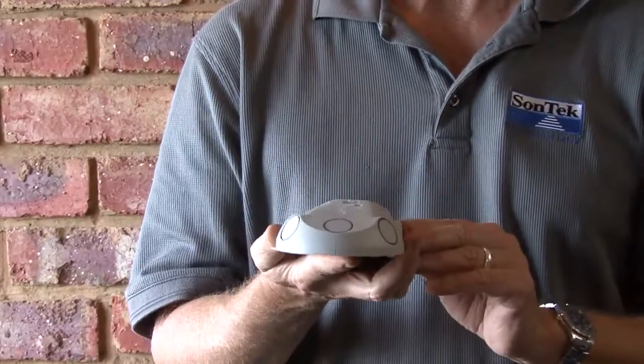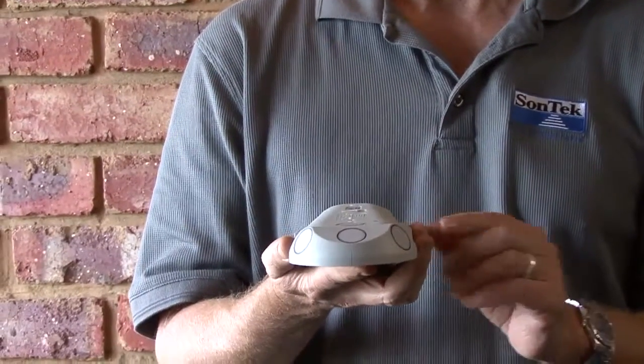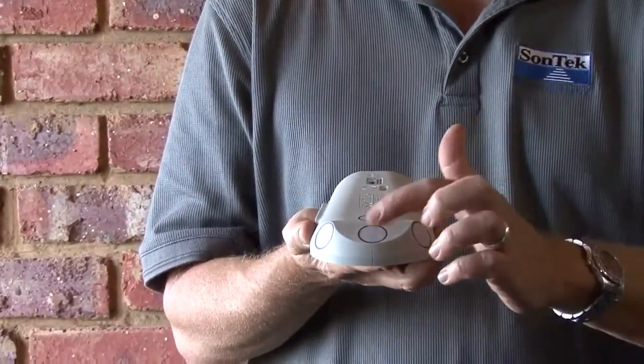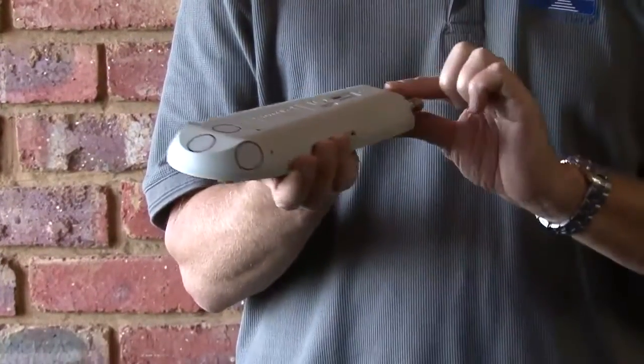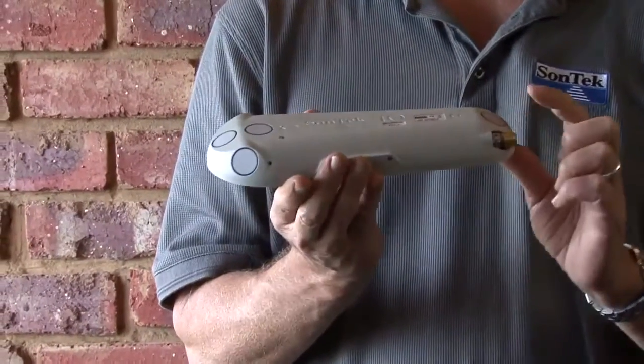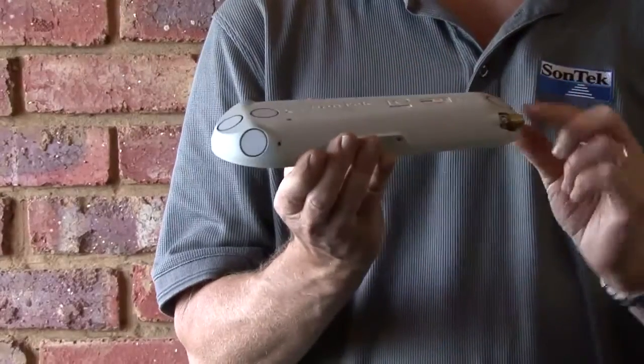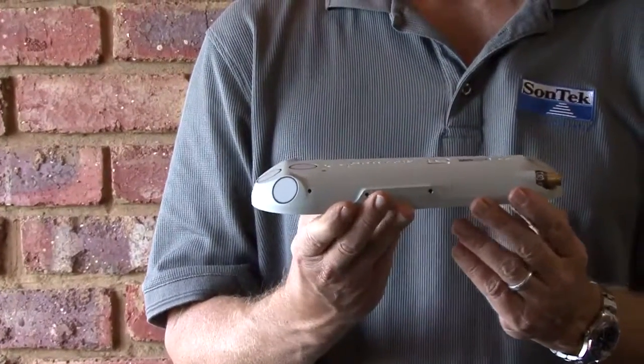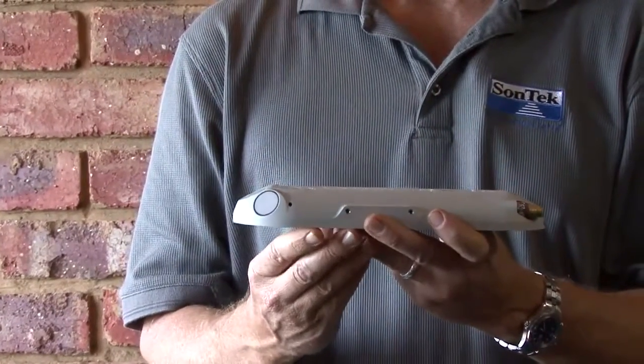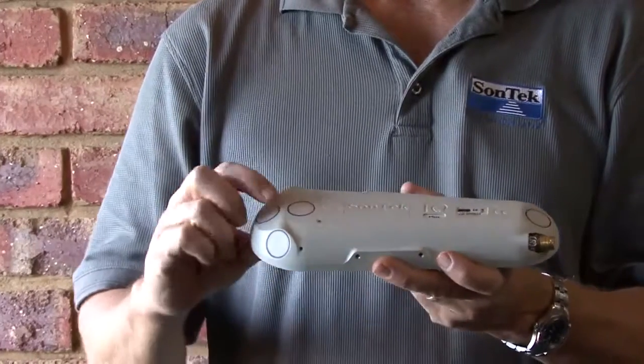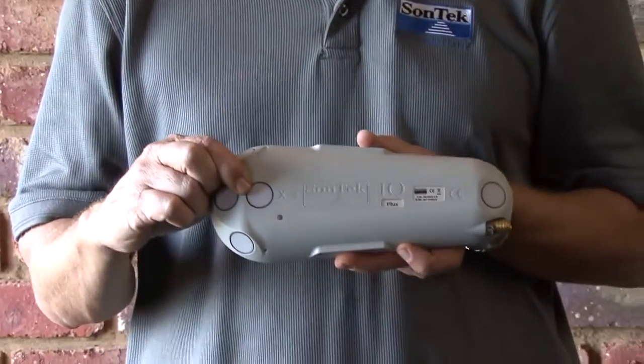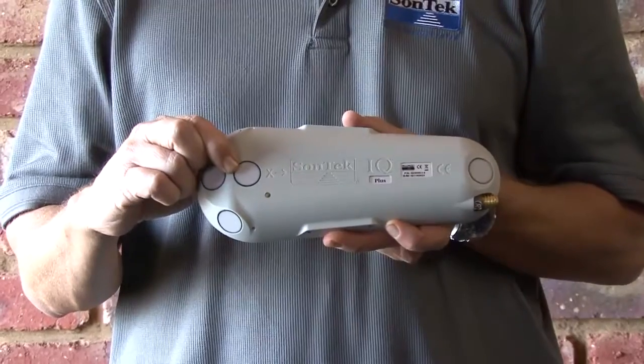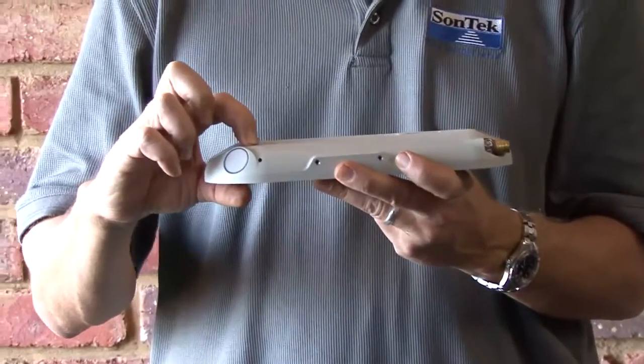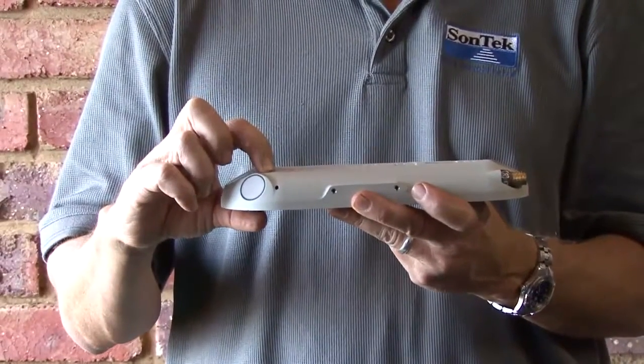We actually use acoustics to measure velocity and water level. These are acoustic transducers. They have a 3 megahertz frequency, and these outside beams here are what we use to scan the velocities in the channel. The next measurement that we need is the water level, and we make that measurement using this 3 megahertz acoustic vertical beam. We also have a pressure sensor embedded inside the housing as a redundant measurement.